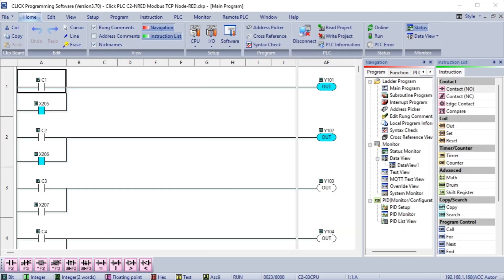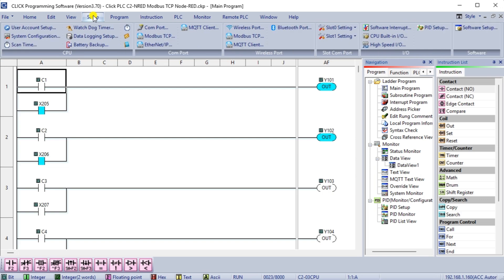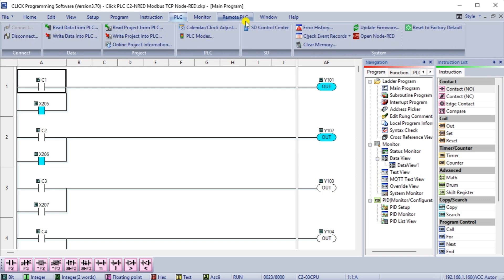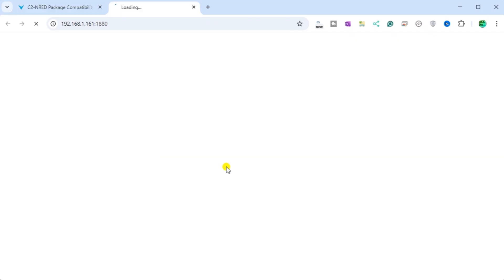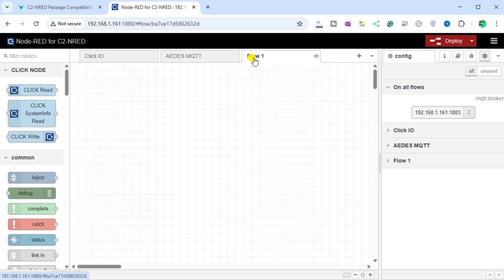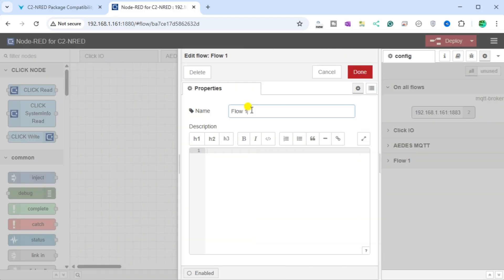We will now set up the C2-NRED Modbus TCP flow to read the BRX Do-More PLC. Open our previous flow using the Click Programming Software by selecting the PLC menu option, then Ethernet, and then Connect. Your default browser will display the flow program we created last time. We will add a tab for our new Modbus communication flow by selecting Add Flow and naming the tab Modbus TCP, then select Done.